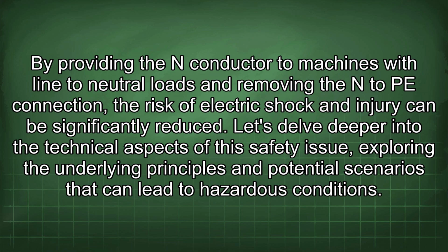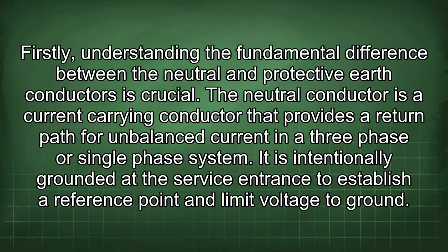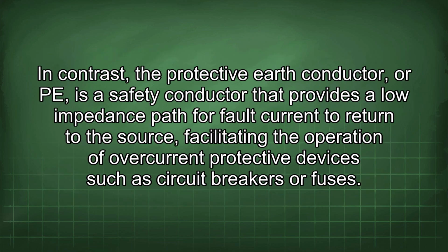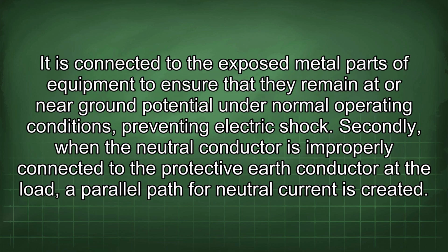Let's delve deeper into the technical aspects of this safety issue, exploring the underlying principles and potential scenarios that can lead to hazardous conditions. Firstly, understanding the fundamental difference between the neutral and protective earth conductors is crucial. The neutral conductor is a current-carrying conductor that provides a return path for unbalanced current in a three-phase or single-phase system. It is intentionally grounded at the service entrance to establish a reference point and limit voltage to ground. In contrast, the protective earth conductor, or PE, is a safety conductor that provides a low impedance path for fault current to return to the source, facilitating the operation of overcurrent protective devices such as circuit breakers or fuses. It is connected to the exposed metal parts of equipment to ensure that they remain at or near ground potential under normal operating conditions, preventing electric shock.